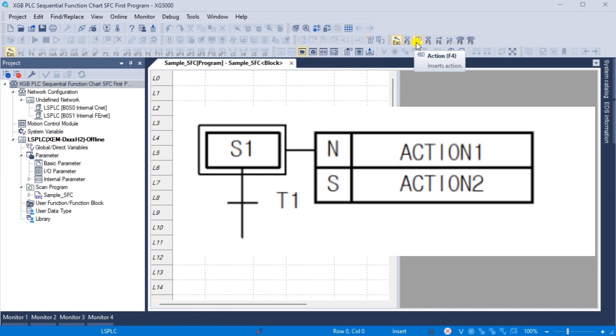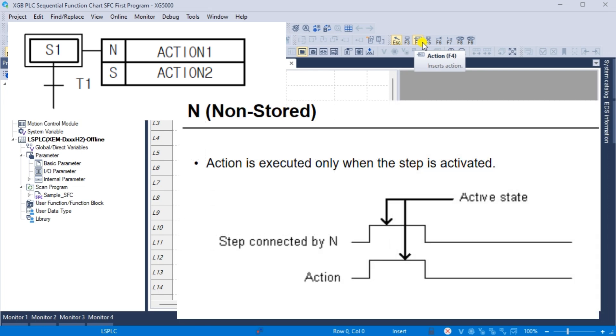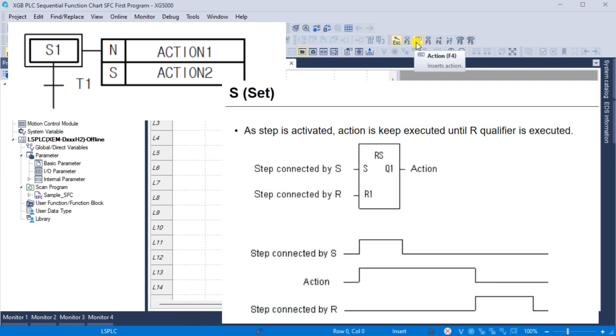Action Qualifier: action qualifiers are used whenever an action is applied. According to the assigned qualifier, the action related to the step defines an execution point and the time. The types of action qualifiers are as follows. N, non-stored: action is executed only when the step is activated. S, set: as the step is activated, the action is kept executing until the R qualifier is executed.